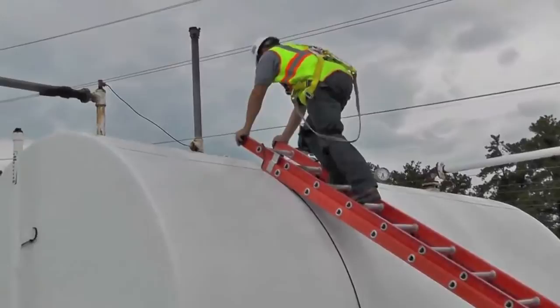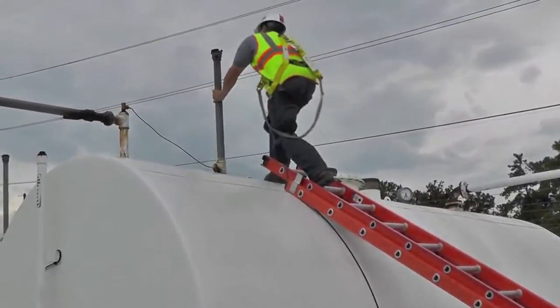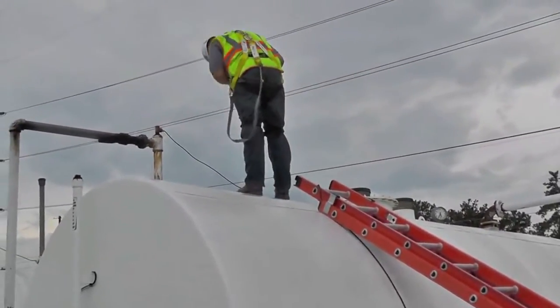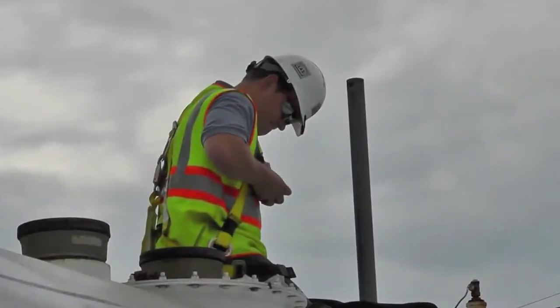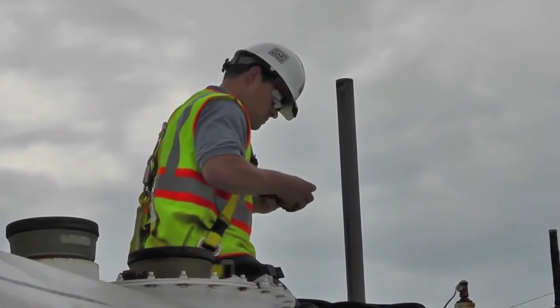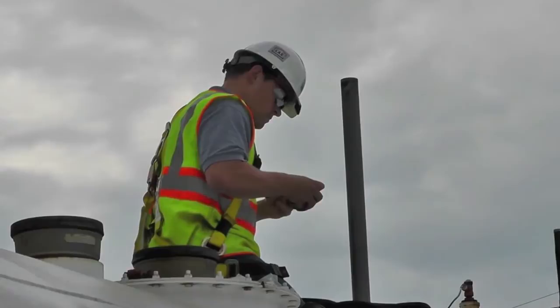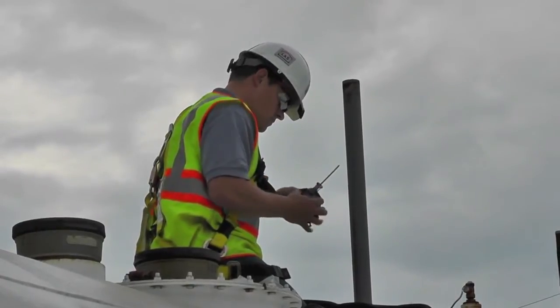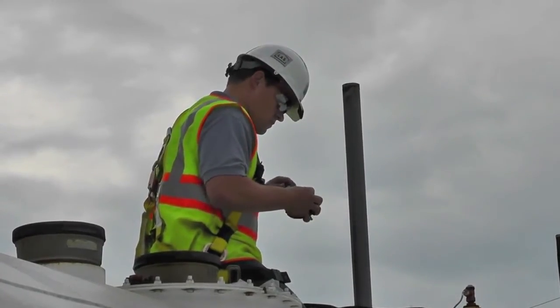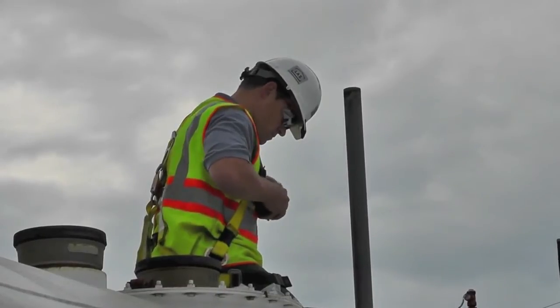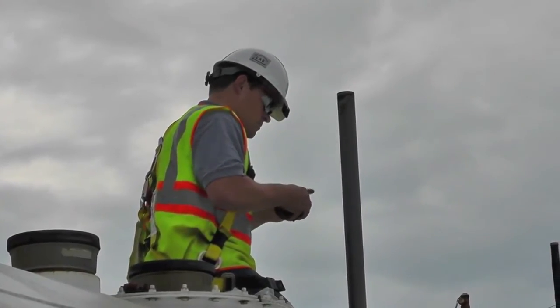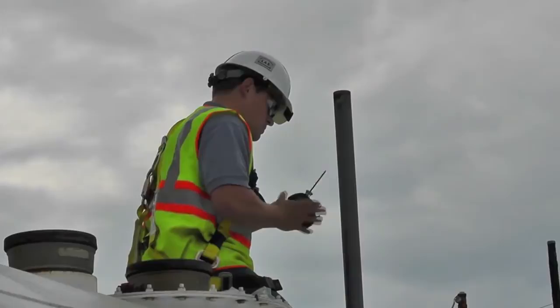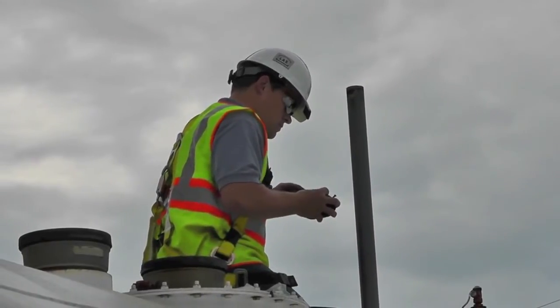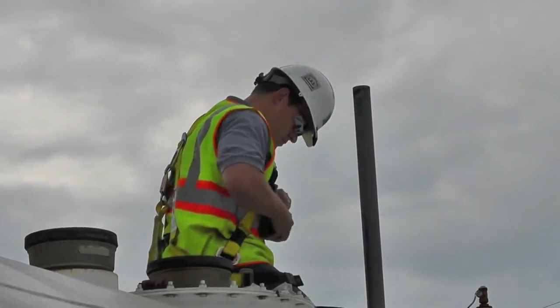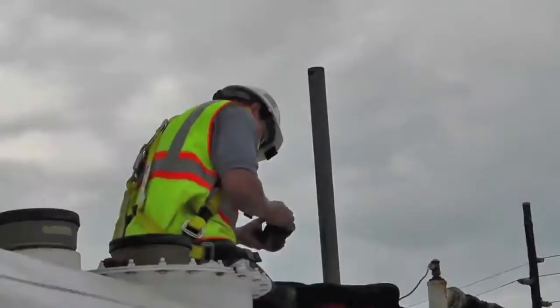Whenever doing an installation on top of a tank, a fall arrest harness is required, no matter the height of the tank. In this installation, we are able to gain access to the tank through an existing breather tube. This is the preferred method for entry because it does not require tank modifications. This particular tank has a precipitation reservoir and a dirt and bug screen. To install the probe, we will remove the cap and create a hole just large enough for our cable to fit inside.